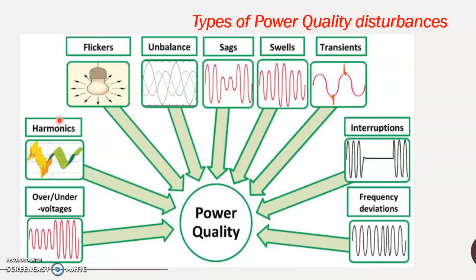First of all, let us discuss the voltage sag or dip in voltage. This is a kind of power quality problem that exists for a short duration of time, so it is classified as a short duration disturbance. Typically, there will be a dip in the RMS voltage over a range of 0.1 to 0.9 per unit for a duration between 0.5 cycles and 60 seconds.